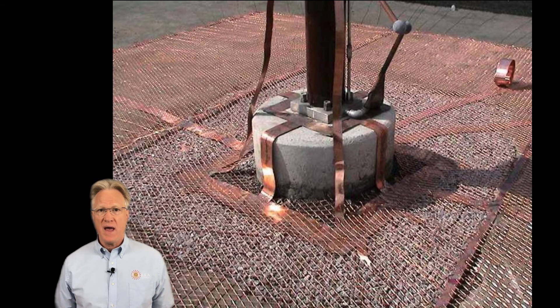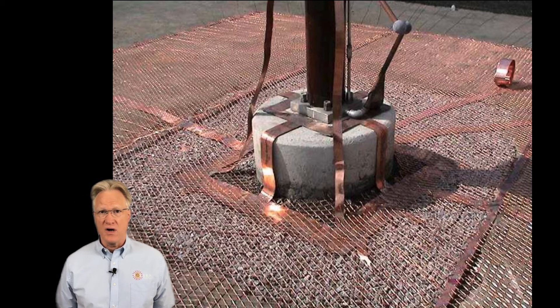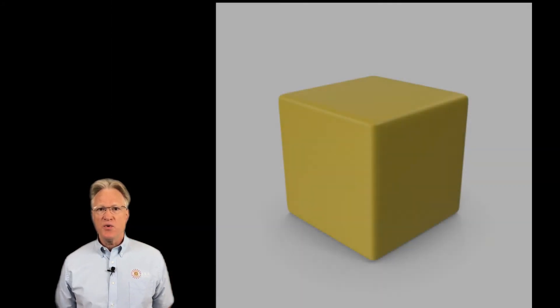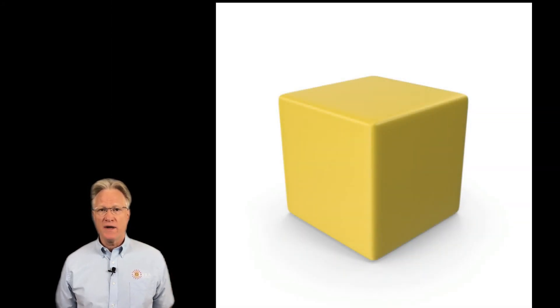Horizontal copper mesh or copper straps interconnecting the multiple ground rods is needed as well. Copper straps in parallel with the ground rods will also help, although this is hard to achieve without lots of excavation. This will build a three-dimensional low inductance cube.